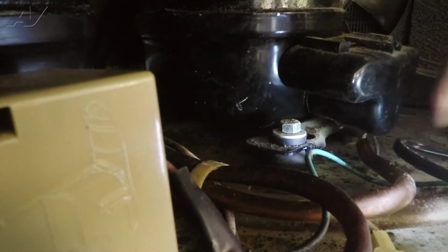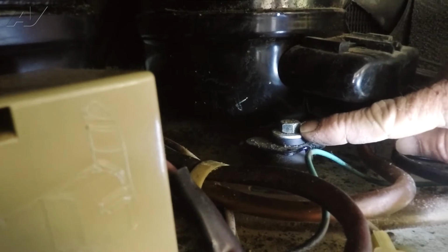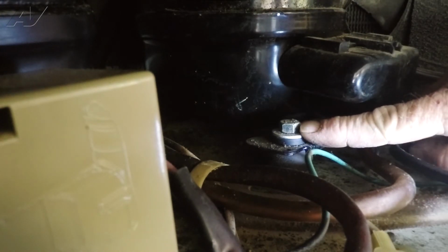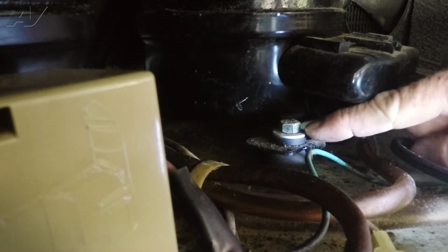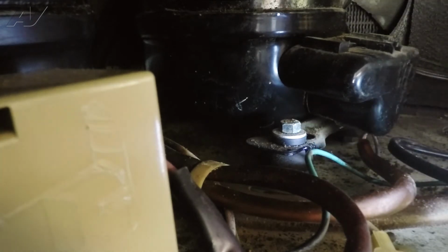Now, in each of the 4 corners of the compressor mounting plate, there are 1/2-inch screws or nuts that hold the compressor onto the mounting bolts that are furnished on the unit. So we're going to need to get those nuts off in order to remove the compressor. Now, once we've got the nuts off, we're going to raise the compressor off of the bolts and just slide it forward like so. And then we'll get our tubing cutter and we will cut the suction line.